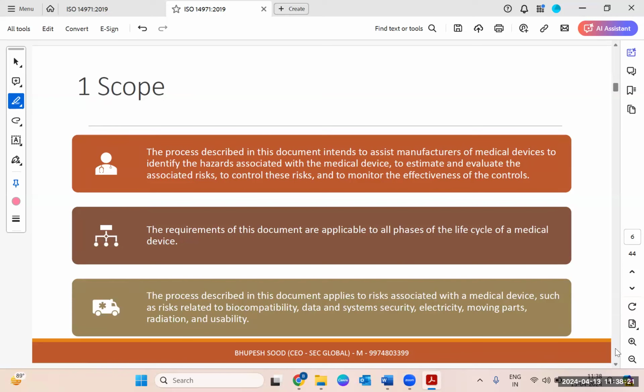This is the scope of ISO 14971, which says that this standard is applicable to all the stages or phases in the life cycle of a medical device. When we say life cycle of a medical device, it means right from conception to disposal. So it is not about when it reaches the hospital and when it is put in the dustbin. It covers the time it is thought of or designed, so from the design phase you also consider the risk analysis. Then from design to commercialization, during the entire shelf life of the product, and at the later stage what happens when it is disposed of. ISO 14971 will always cover all the stages.